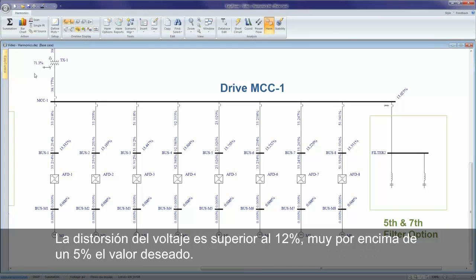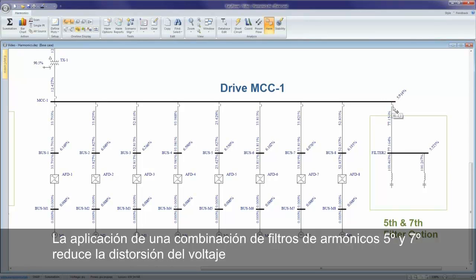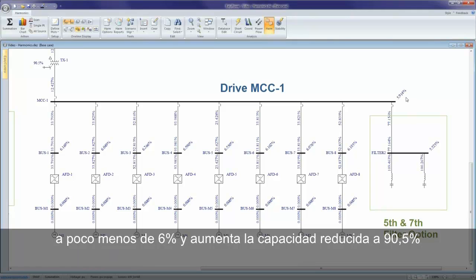The voltage distortion is over 12%, which is far above a 5% desired value. Applying a 5th and 7th harmonic filter combination drops the voltage distortion to just under 6% and increases the derated capacity to 90.5%.